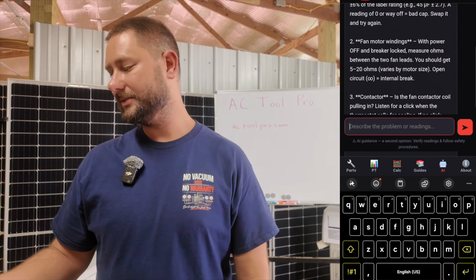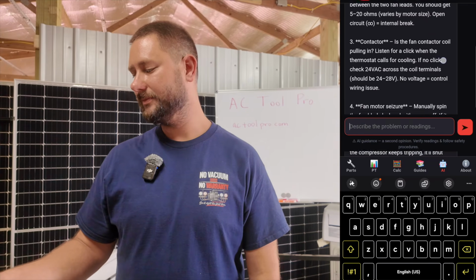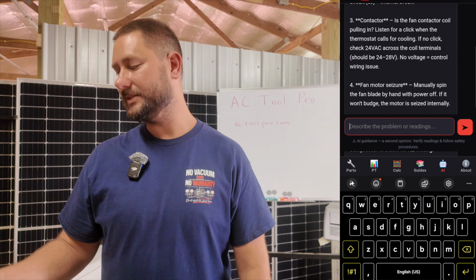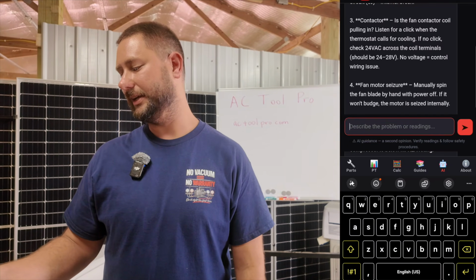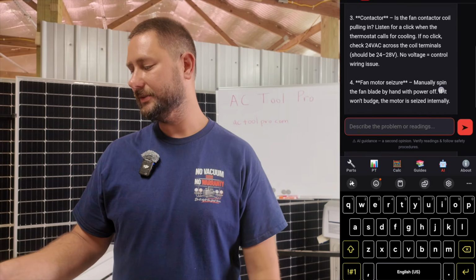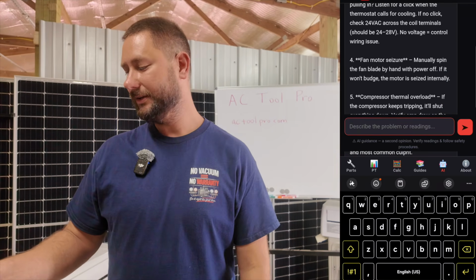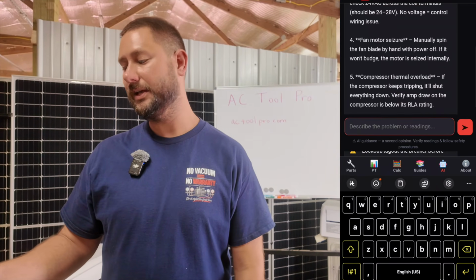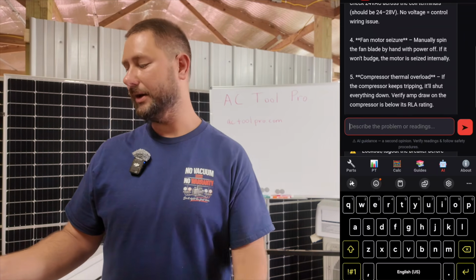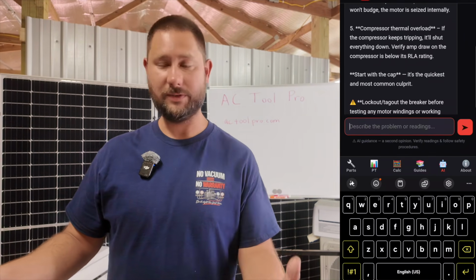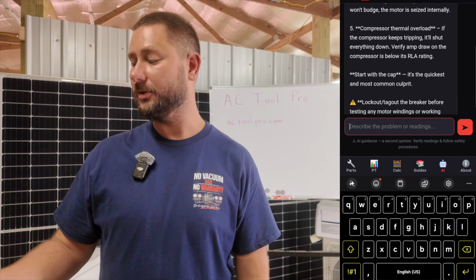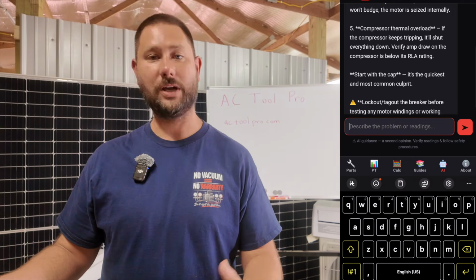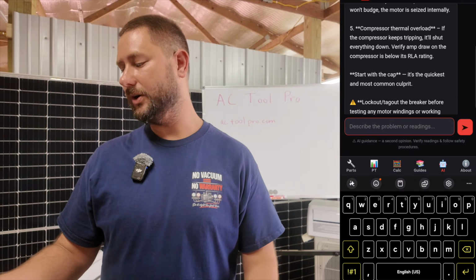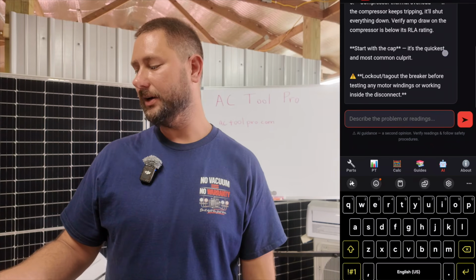Fan motor windings. Turn off the breaker, measure the ohms. Contactor. Is the fan contactor coil pulling in? So check the contactor, check, see if there's a call. Fan motor seizure. Manually spin the fan blade by hand with the power off. So seeing if it's seized up. Compressor thermal overload. If the compressor keeps tripping, it'll shut everything down. Verify amp draw on the compressor. Is it below its RLA?